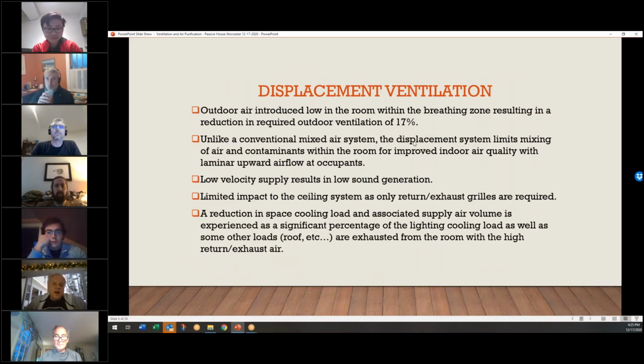Displacement ventilation. Why do we use it? In the schools, we use it extensively in classrooms. Most of the new schools we've been doing for the last several years have been displacement in classrooms. Again, the benefit is we're trying to get the air into the breathing zone. So we put it in low. It comes in very slow, like 50 feet per minute out of the diffusers. Usually the diffusers are along the wall. The air comes in and just hits the people and blankets them in their dedicated outdoor air, fresh air, tempered, obviously. And then the heat plume takes it up and out of the room.